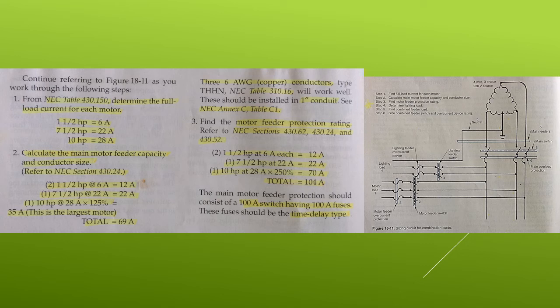Step 3, find the motor feeder protection rating. Refer to NEC sections 430.62, 430.24, and 430.52. So we have two 1.5 horsepower at 6 amps each, or 12 amps total. We have one 7.5 horsepower at 22 amps, so 22 amps for that. And we have one 10 horsepower at 28 amps, which we multiply by 250%, giving us 70 amps. Adding all those amps, we have a total of 104 amps. So the main motor feeder protection should consist of a 100 amp switch having 100 amp fuses. These fuses should be the time delay type.